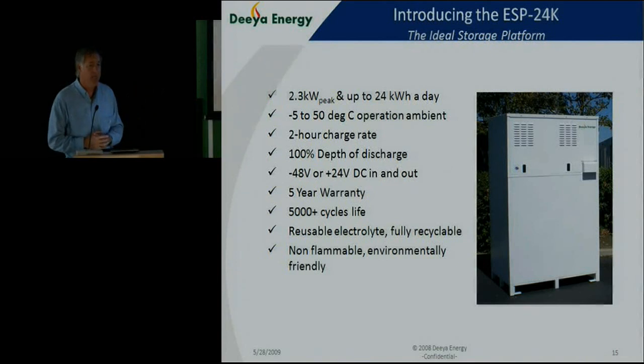Also, I should mention that the battery can be designed to support various voltage ranges that are very standard for both telecommunications and UPS applications. The electrolyte at the end of the life of the system is reusable and recyclable. We can take the electrolyte, remove the core elements of the system, which are basically chromium and iron, and then rebuild the electrolyte for use at a later date. So the electrolyte basically has an infinite life. It's not flammable. There are no emissions that the system puts out. There are no hydrogen emissions. So it's, again, a very safe, benign technology that can, in fact, be used indoors.